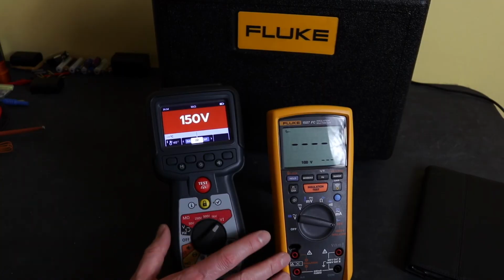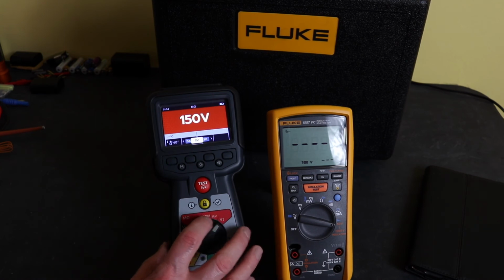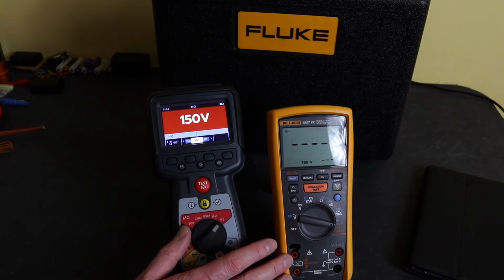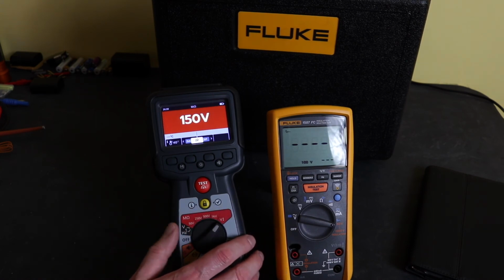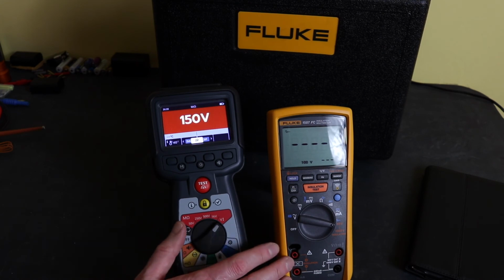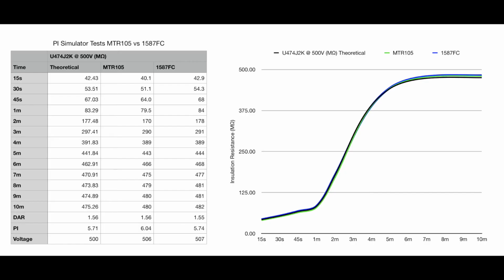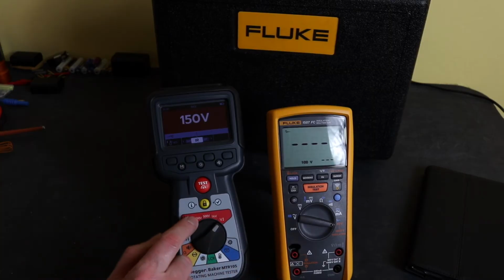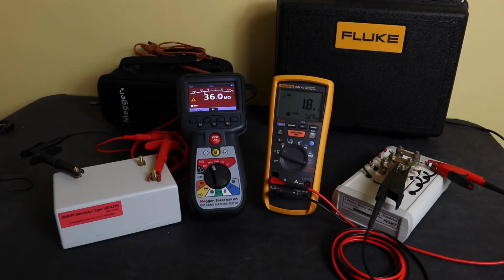So between the two instruments for polarization index, there wasn't an awful lot to pick between them. I'll stick the curve up from the test module. They were both pretty accurate. This was more accurate with the DAR result than the 1587, and for the polarization index, this was a bit better than the MTR105, so 50-50 on that one, really. So you do get a difference with the end result when you're doing polarization index testing.